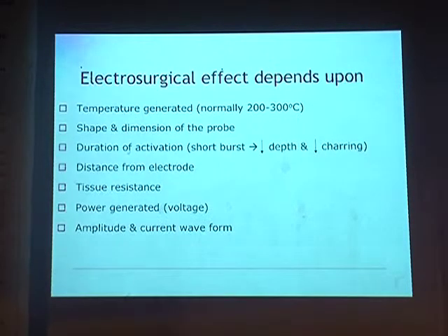So altogether, the electrosurgical effect depends on the temperature generated, the shape and dimension of the probe because of current density, distance from the electrode, tissue resistance, and definitely the power and amplitude of the current. Altogether, the whole effect will come out.